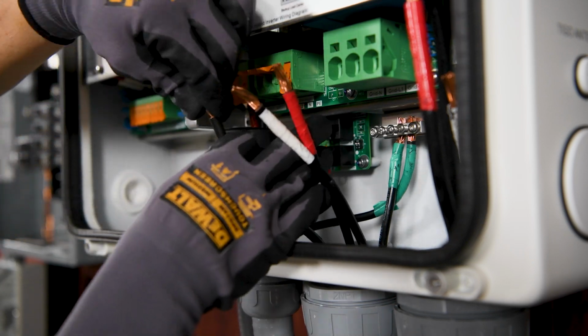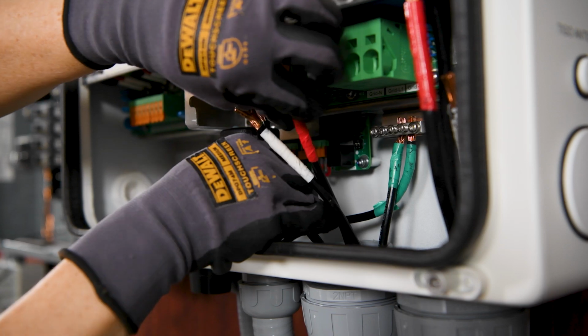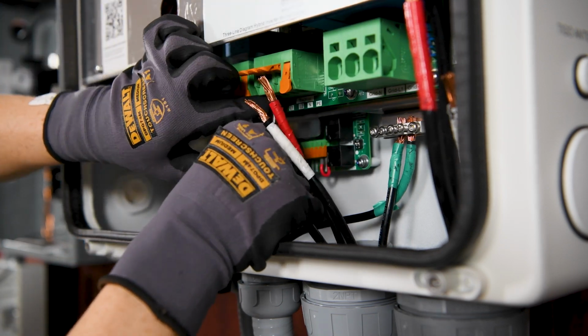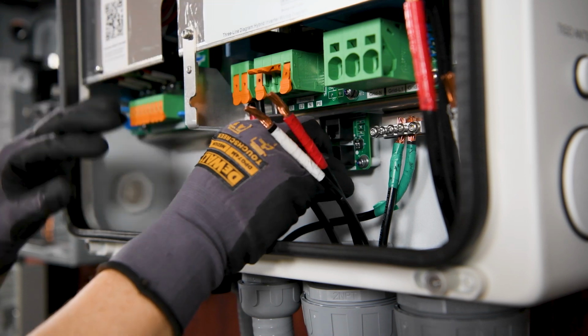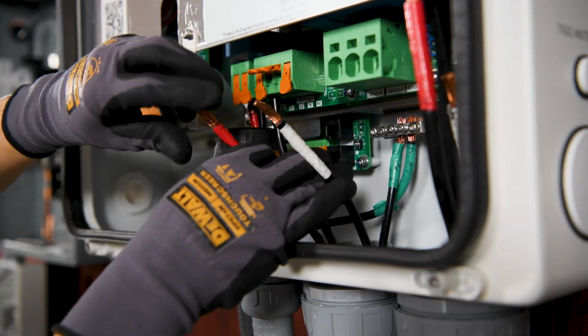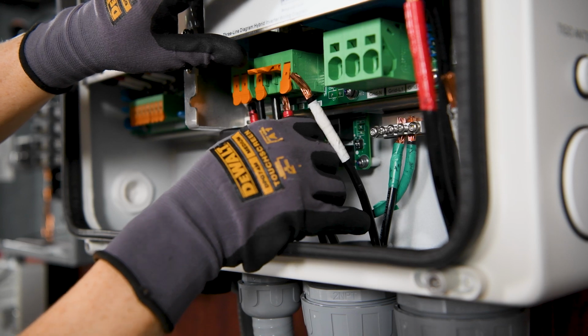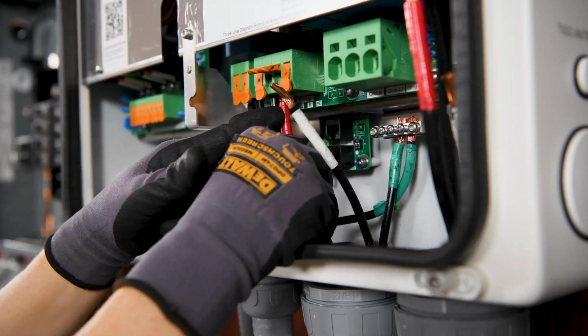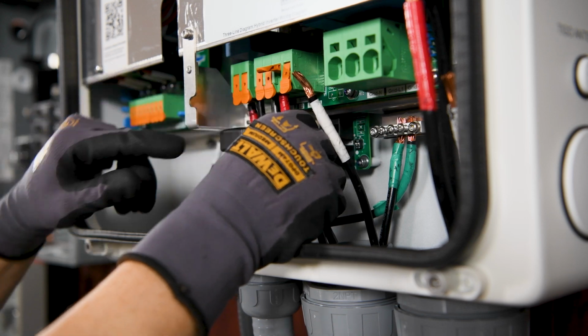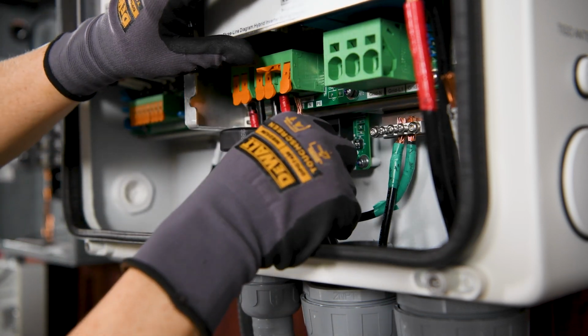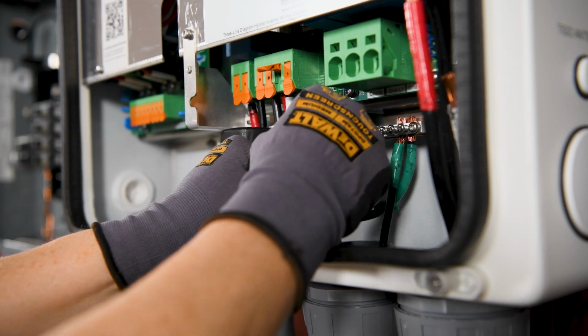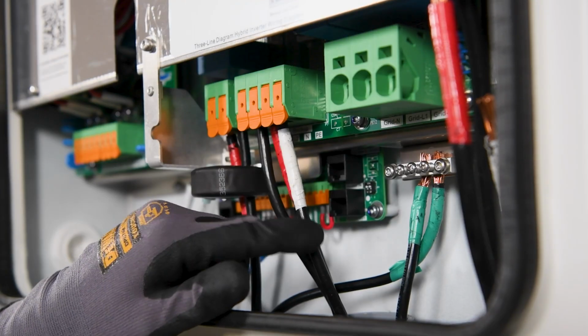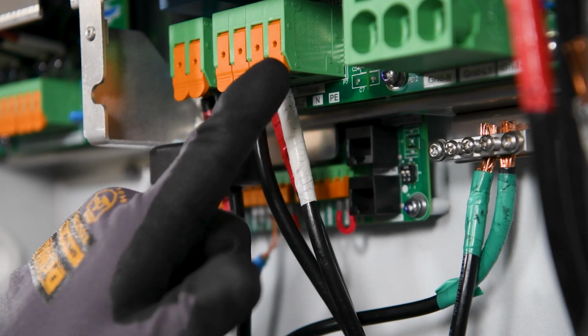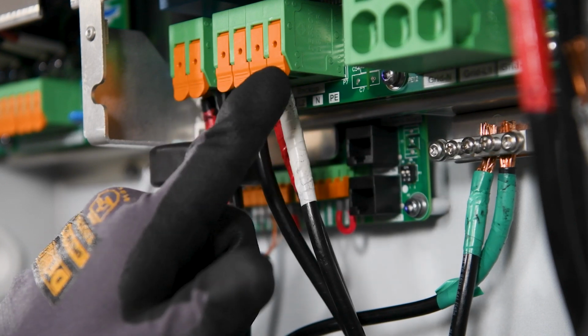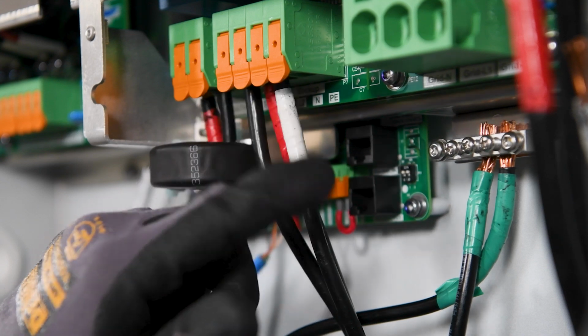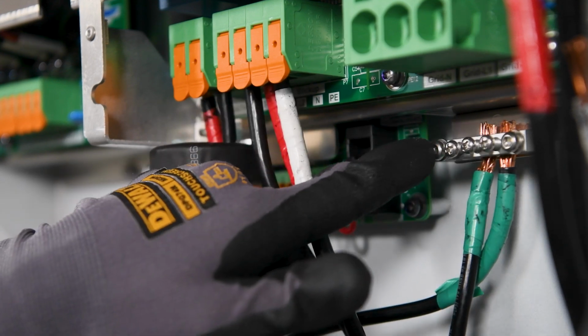So we'll take our L1, black, flip up your orange tab, insert it into the terminal block, flip down the orange tab, and give it a gentle tug. And we'll follow up with L2, and neutral. One thing to note is this 4th terminal labeled PE is a dead lug. It is there to reference ground, but do not use this one for your ground. Always use your grounds for this ground bar down below.